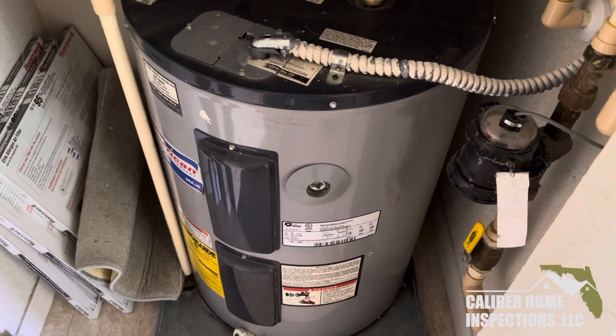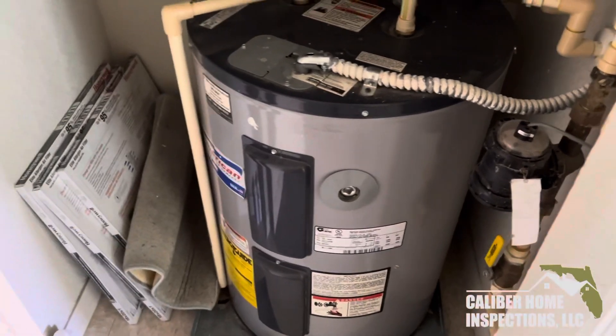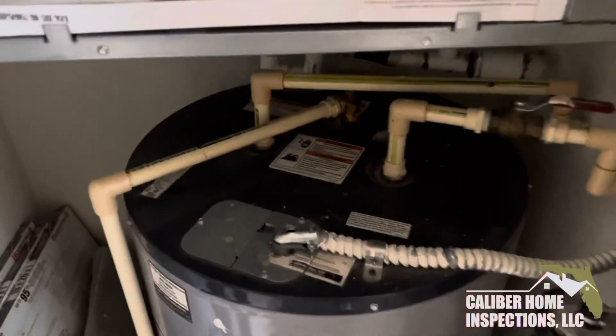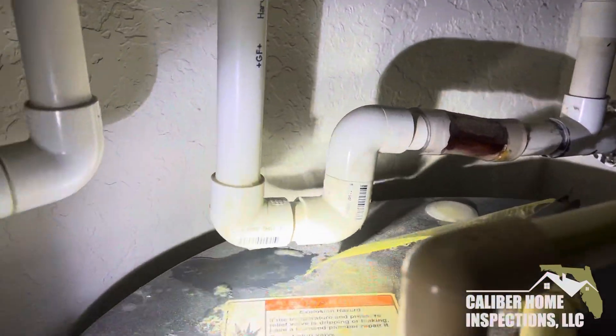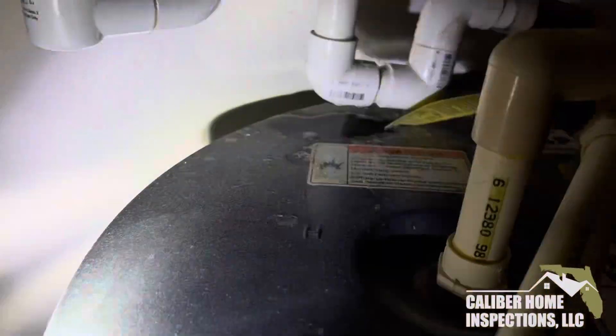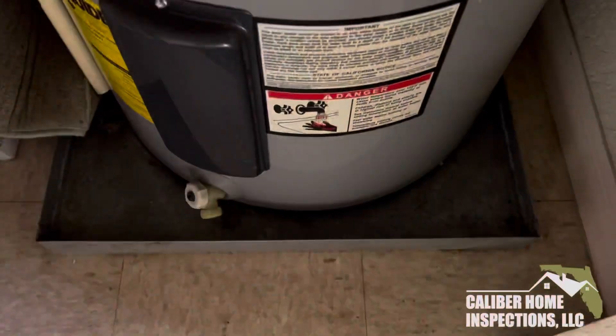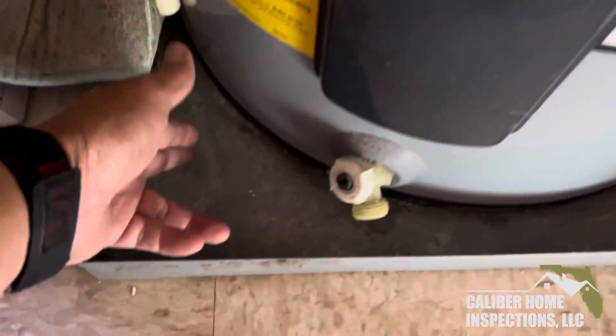This is Paul, Caliber Home Inspections. I'm inspecting a condo which is currently vacant. Here's the water heater and the AC. What we have going on here is there's a leak at the condensate line right there — you can see the water leaking down into the drip pan for the water heater.